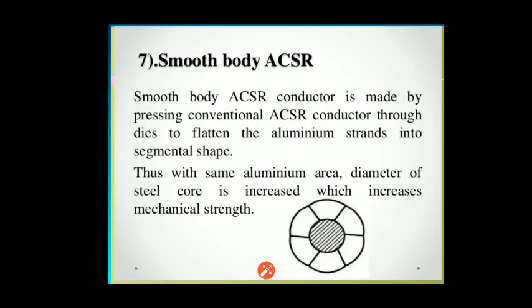Seventh, the smooth body ACSR conductor. As shown in the diagram, it is made by pressing the conventional ACSR conductor through dies to flatten the aluminium strands into a segmental shape. With the same aluminium area, the diameter of the steel core is increased, which increases the mechanical strength. This type of conductor has high mechanical strength and good mechanical capability.